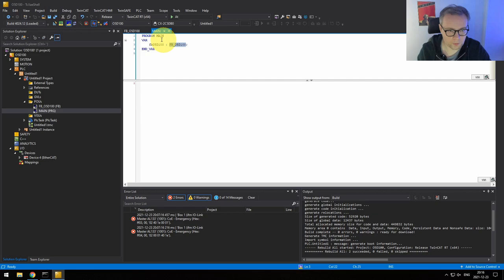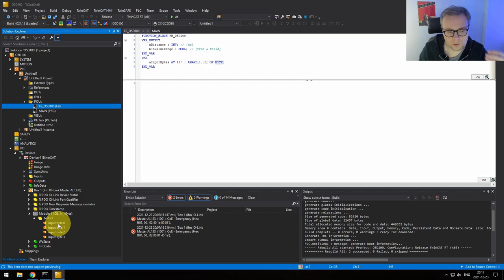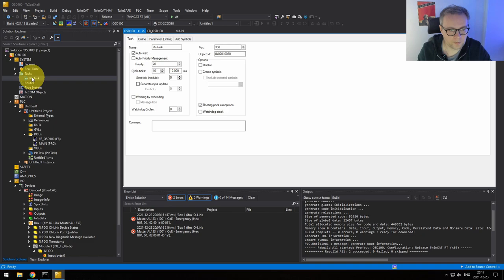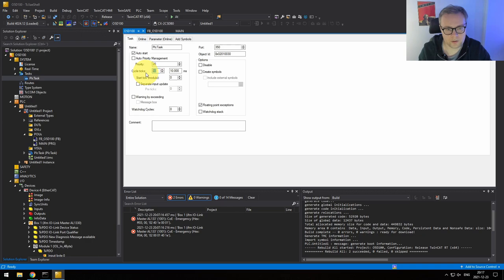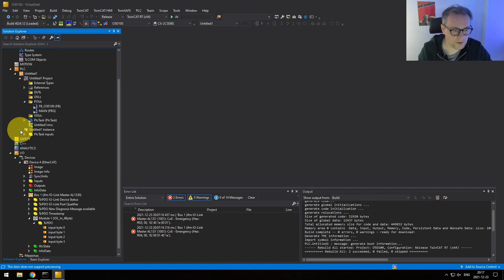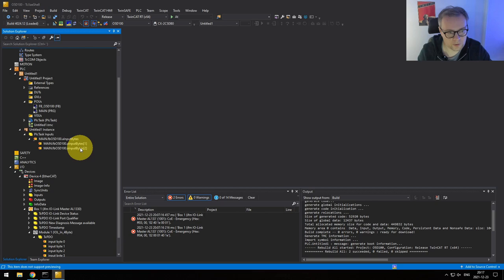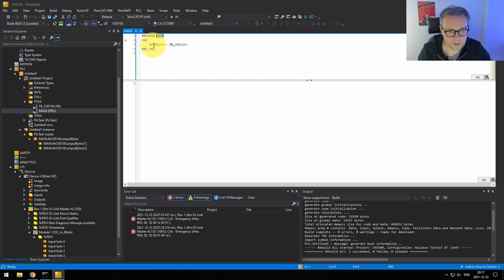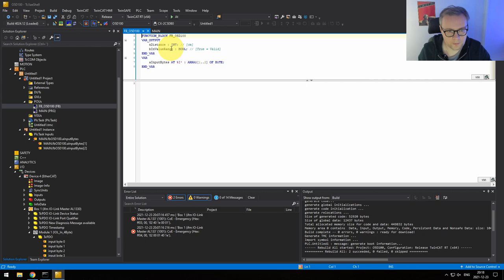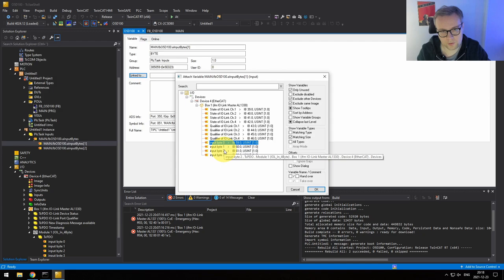Going back, I've compiled the program and now have a main program. We need to link the bytes both to get the data from the IO-Link slave and so the EtherCAT master knows how fast to run. Our PLC task is running at 10ms, so that's the speed at which EtherCAT will run. In the IO tree we can see the variable names — main.fb.aInputBytes — and we click 'Link To' to link Input Byte 0 and Input Byte 1. We skip Input Bytes 2 and 3 since the sensor only sends 2 bytes.